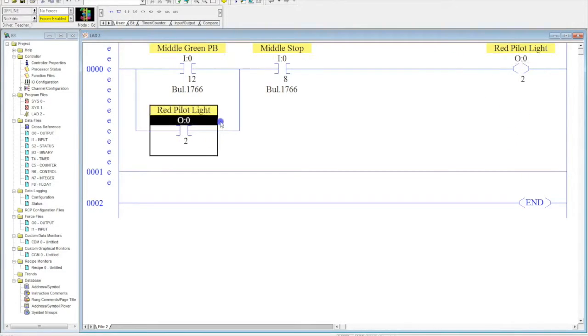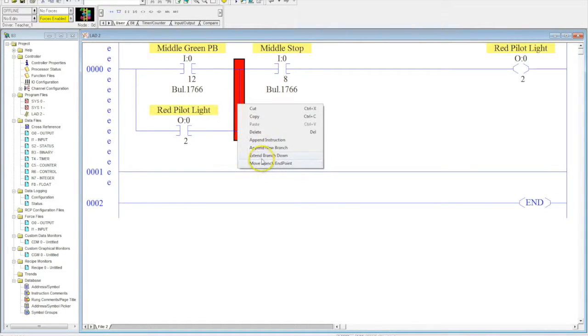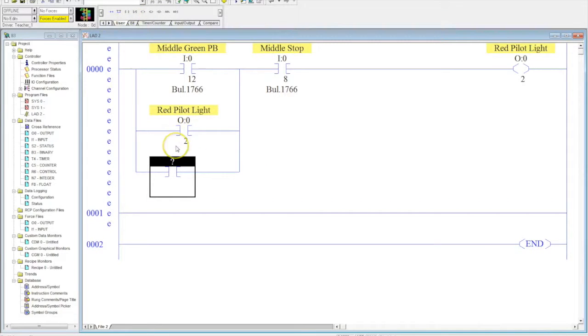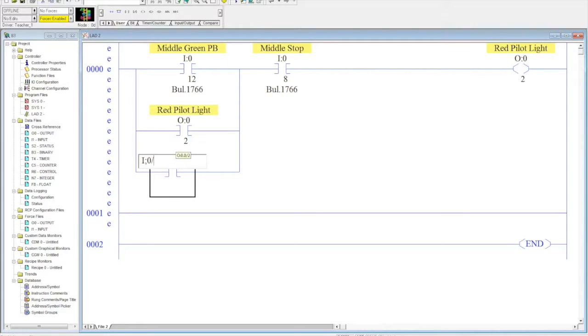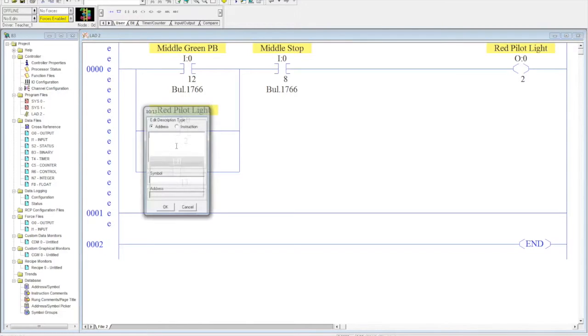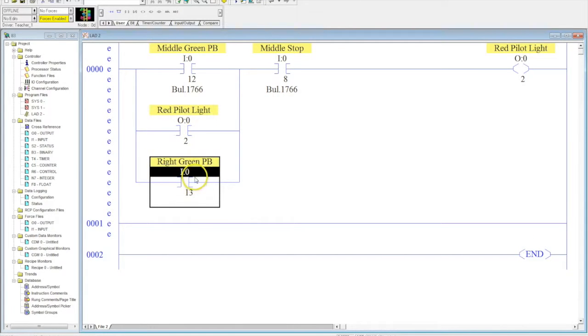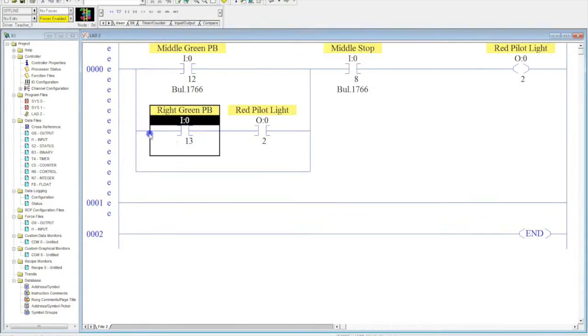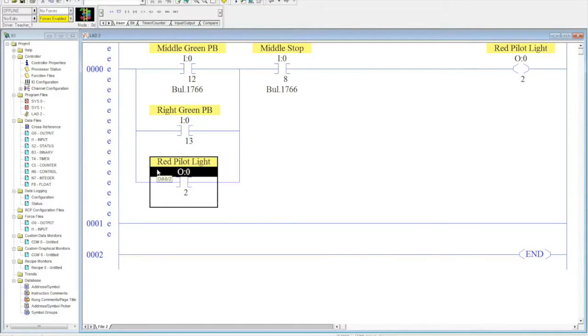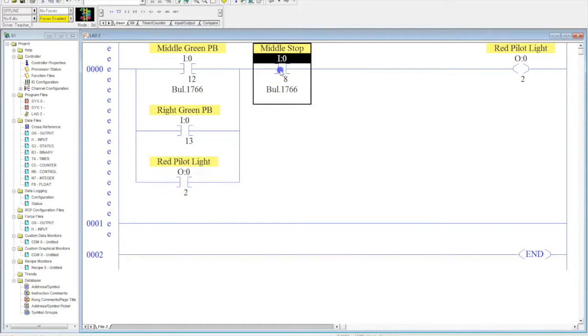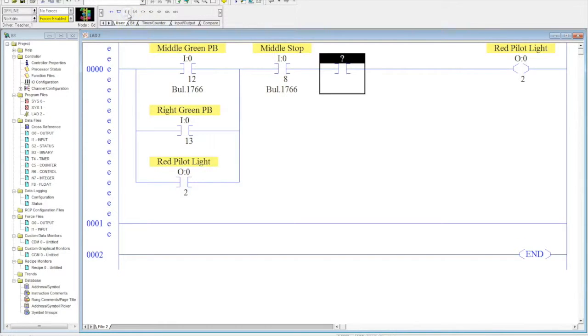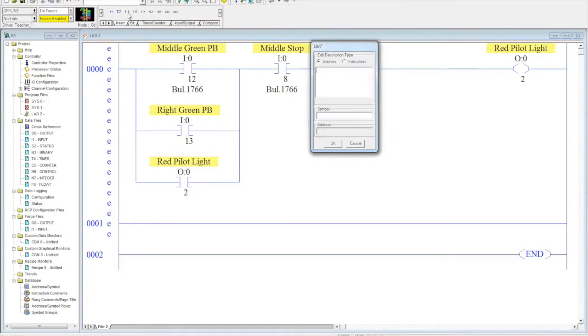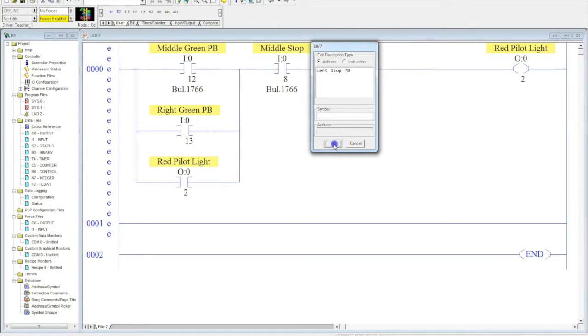Drag that memory right over here. Now, if I wanted to put another start stop station in here, what I'd have to do is right click, extend branch down, grab another input, and then identify another start button. We'll use number 13 here, which is our right green push button. Now some people will say the memory always has to be at the bottom. I don't disagree with that, so I'll switch those two real quick. Then we're going to use a different stop button. I colon zero forward slash seven. This will be our left stop push button.